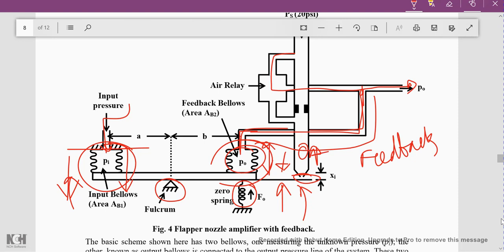When the required pressure and the set pressure are equal, the flapper returns to its original position. If anything changes in the input, the flapper position changes, the output pressure changes, and through the bellows the controlling action is obtained. This second bellow is itself called the feedback bellow, to which the input signal is given from P0. Depending upon its expansion and contraction, the output value is controlled.